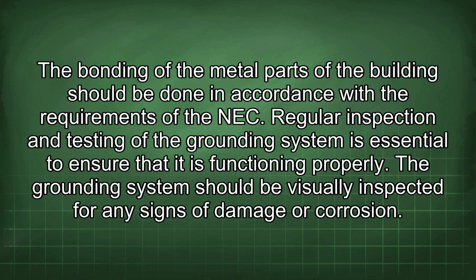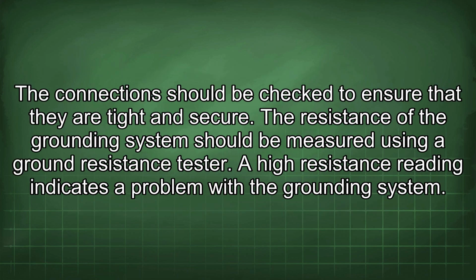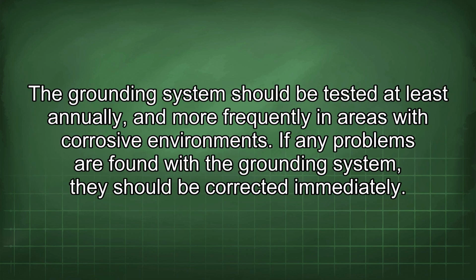Regular inspection and testing of the grounding system is essential to ensure that it is functioning properly. The grounding system should be visually inspected for any signs of damage or corrosion. The connections should be checked to ensure that they are tight and secure. The resistance of the grounding system should be measured using a ground resistance tester. A high resistance reading indicates a problem with the grounding system. The grounding system should be tested at least annually and more frequently in areas with corrosive environments. If any problems are found with the grounding system, they should be corrected immediately.